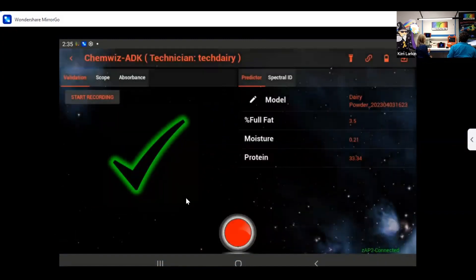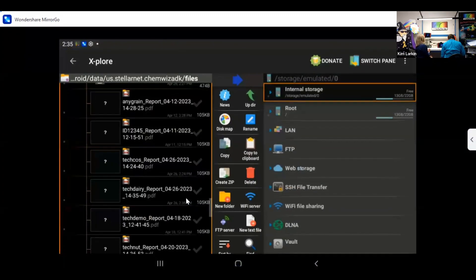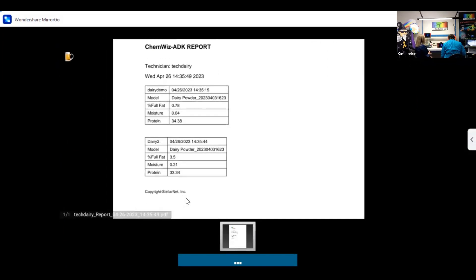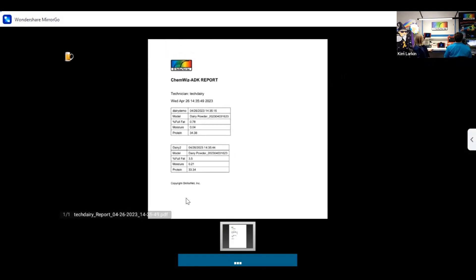You can see the location that the data file is saved to. It will populate your tech dairy report, and it's going to have the technician, the model, the fat, moisture, and protein for the two samples. This is our standard report — we can actually customize and modify the reports. With our admin demo you can add other things and measure things like lactose, salt, pH, etc. But this is our technician demo, so thank you for watching and let us know if you have any questions.